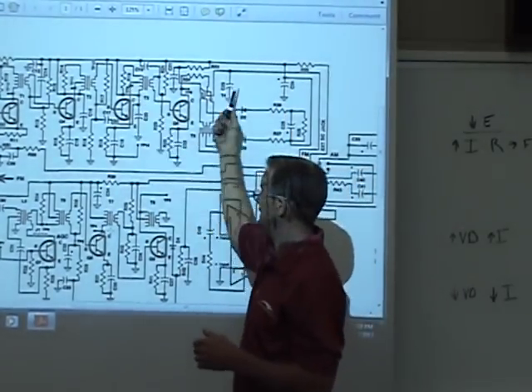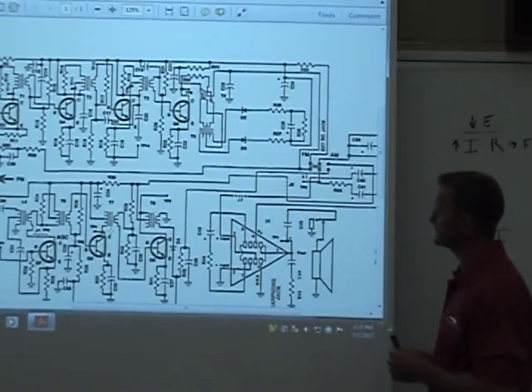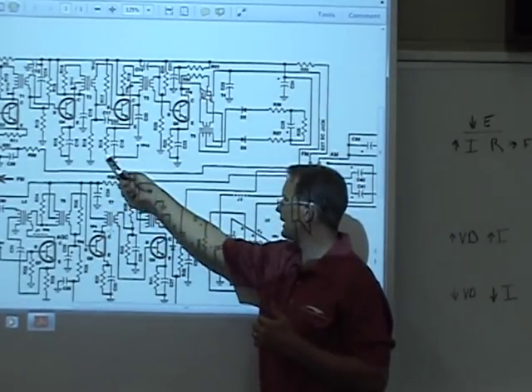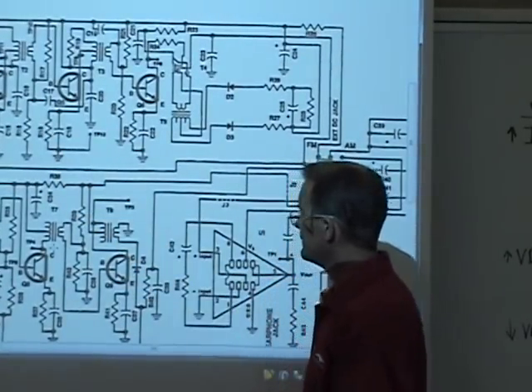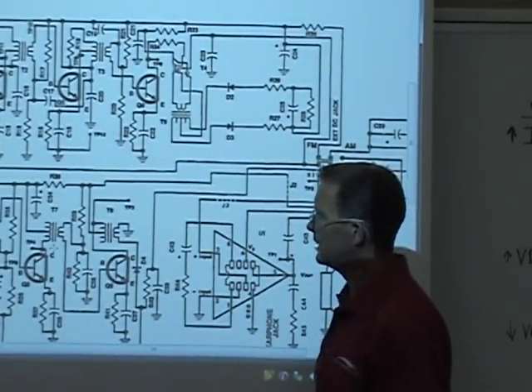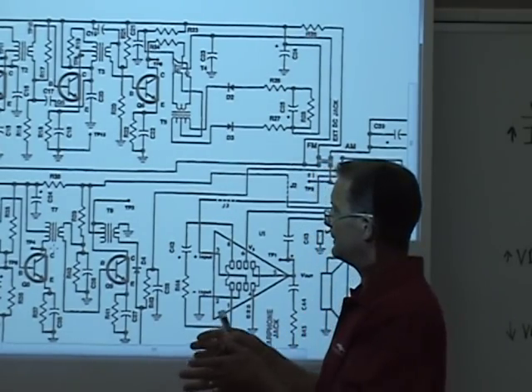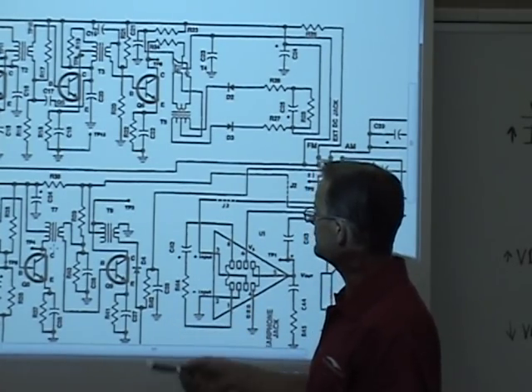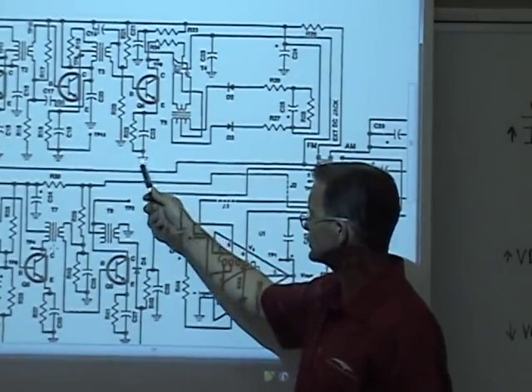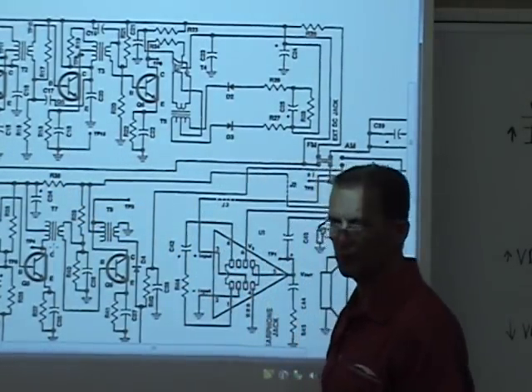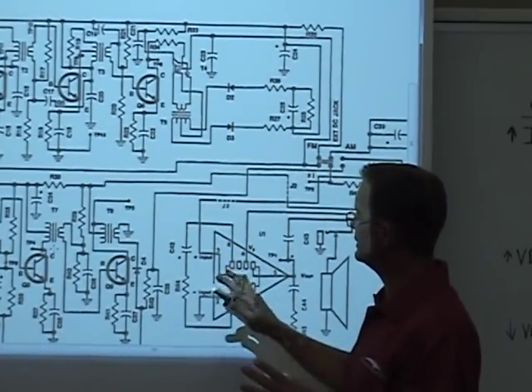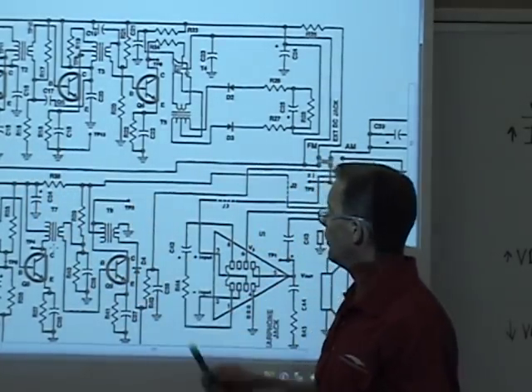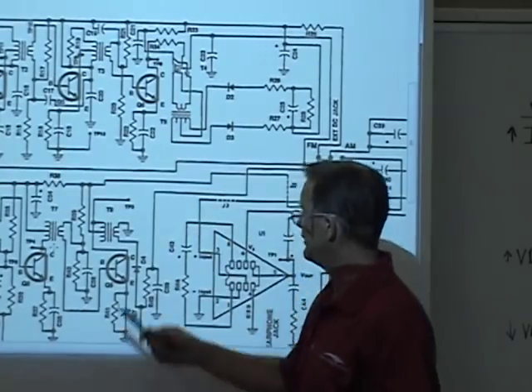Now what I'm going to do in this system is I'm going to come to my components at my grounding points, right above my grounding points, my capacitor and my resistor, and I'm going to take voltage drop readings across those and compare them with my known good system and my troubled system. And what I'm going to find is I'm going to find my leak. I'm going to find my leak because whichever source to ground here has the highest current flow, then I'm going to be able to determine, I'm going to be able to isolate whether it's this system, this, this, or this. Once I isolate it, let's say this right here, I have a high current flow here.